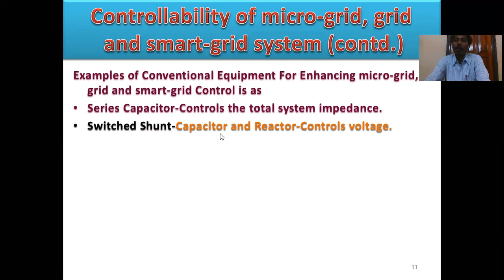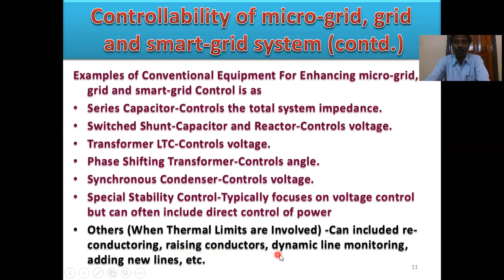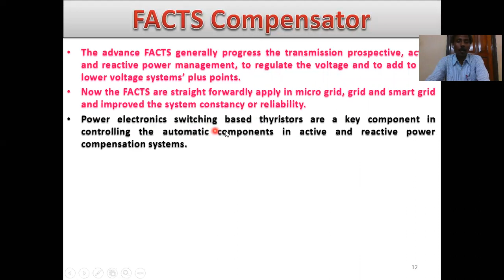Synchronous condensers control voltage. Special stability controls typically focus on voltage control but can often include direct control of power. Others, when thermal limits are involved, can include reconductoring, raising conductors, dynamic line monitoring, adding new lines, etc. FACTS compensators: the advanced FACTS generally improve transmission potential, with active and reactive power management to regulate the voltage and to add the lower voltage system plus point. Now FACTS are straightforwardly applied in microgrid, grid, and smart grid and improve the system stability and reliability. That means FACTS controllers control the system stability and reliability.